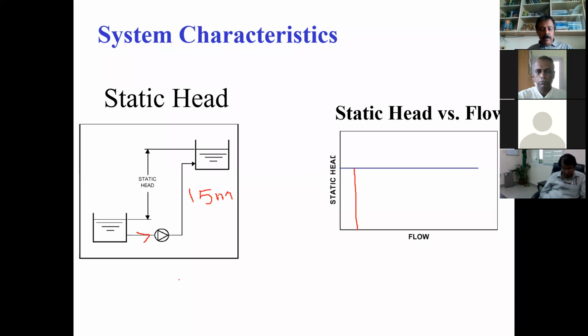If the pump is going to pump at the rate of 50 meter cube per hour, again it has to lift the height of this 15 meters. So this 15 meter is what we call static head, the vertical height from the pump discharge to the delivery of the tank. And if you're going to pump at 100 meter cube per hour, again it has to go to a height of 15 meters. So irrespective of the flow rate, the static head is going to remain constant. It doesn't change with the rate of flow.